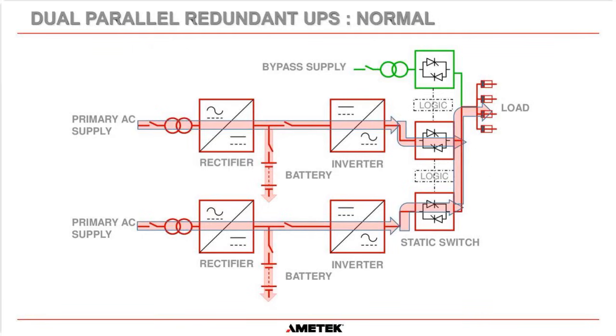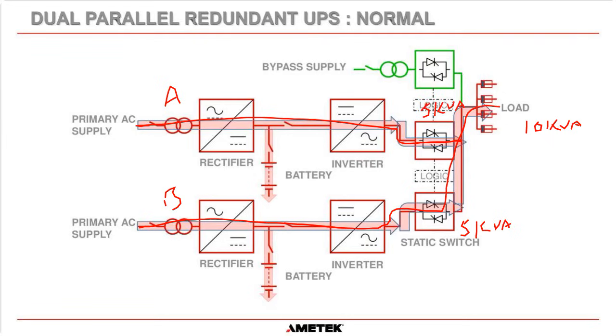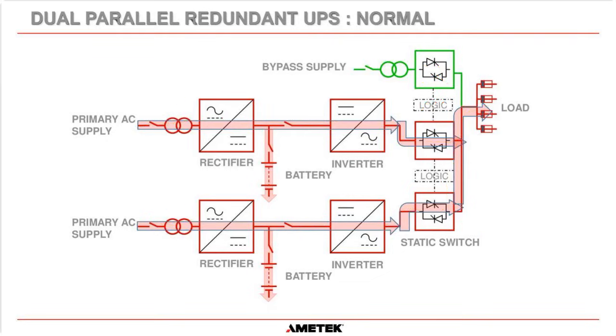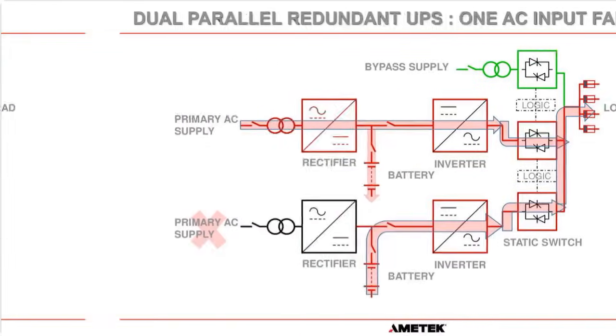And it's the same as always. The red is showing you power flow. In normal operation, we'll call these UPS B and UPS A, both UPSs should be sharing the load. So let's say the load is 10 kVA. Then this UPS will supply 5 kVA, and this UPS will supply 5 kVA. The bypass supply is still there, ready to go if necessary, but this static switch is off. It's waiting to be turned on in case there is an issue with both of the UPSs. But that is normal operation for a parallel redundant system.